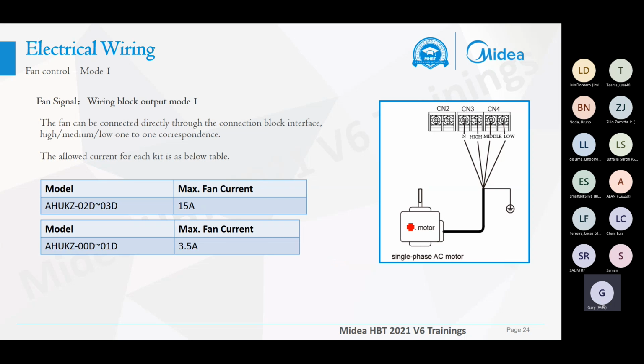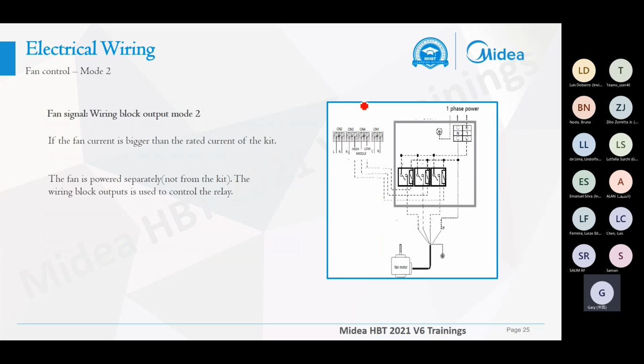Okay, this is the maximum current we measured before. For the 00 and the 01 kits, the maximum current is 3.5 amps, and for the 02 and the 03 kits the maximum current is 15 amps. If the current is over this maximum, we should use a relay, and then connect to the fan terminals of the main block.